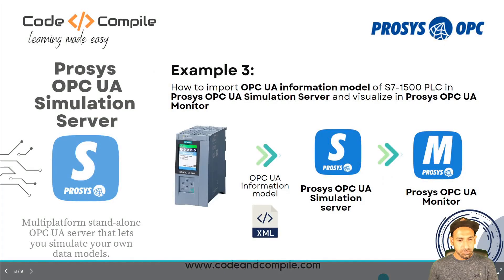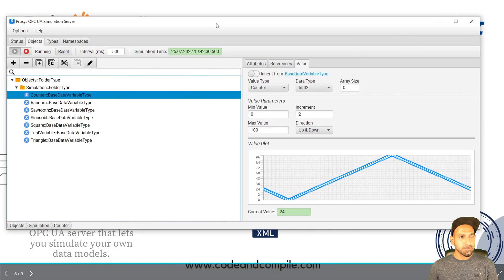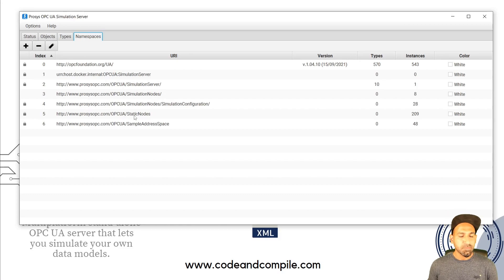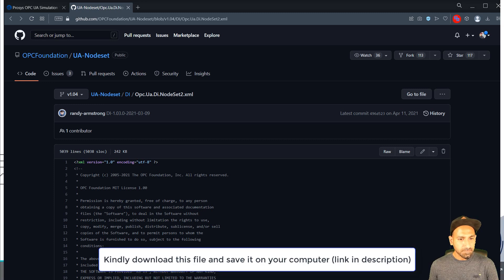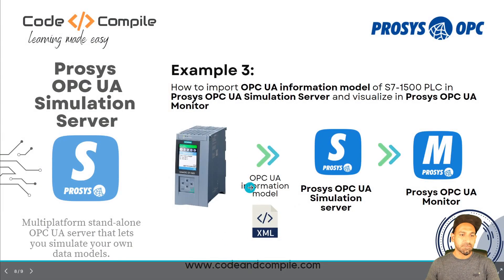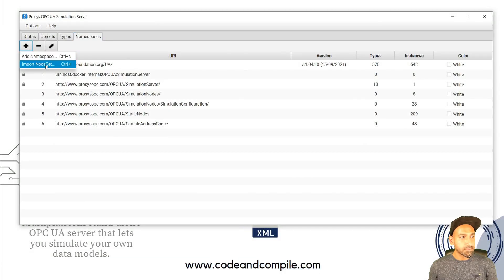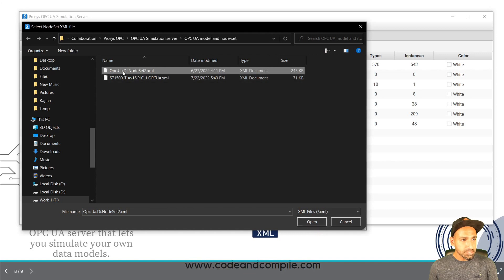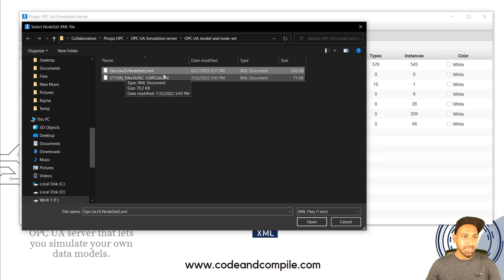Now come to the OPC UA Simulation Server. Go to Namespace. When importing this XML file, you need to understand that it references an OPC UA model defined on GitHub. You must import that GitHub file first, then import the XML file exported from TIA Portal. Every PLC has a specific way to define its OPC UA model. In the simulation server, click Plus and select Import Node Set. Import the predefined node set file for the Siemens PLC — you can find the link in the description on the GitHub account.